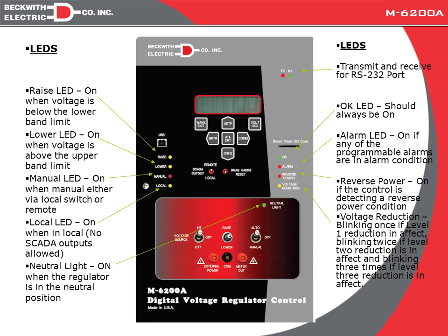And then the next LED down is the local LED. This LED is driven solely off the remote local switch. So in the remote position, SCADA has full control of this particular control. In the local position, you are in a read-only from SCADA. So we will still respond to analog input requests, digital input requests, class polls, but we will not accept any setting changes via analog outputs or any controls via binary outputs.